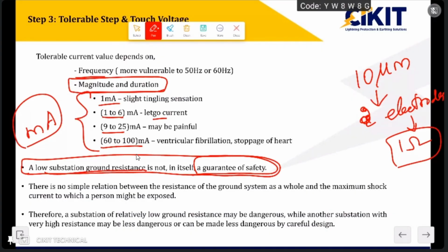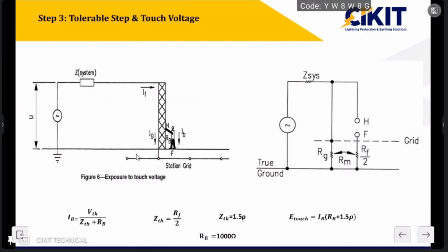Here we can observe that a substation with relatively low ground resistance may be dangerous in some cases. Even though the ground resistance is lower, it can be considered dangerous. So the ground resistance value does not have a direct relationship with safety, and only with a lower ground resistance value we cannot tell that the site is safer. If you are going for a substation, the design parameters for equipment are the step and touch voltages. This is how we will be calculating step and touch voltages. It is a little bit of a complex calculation.